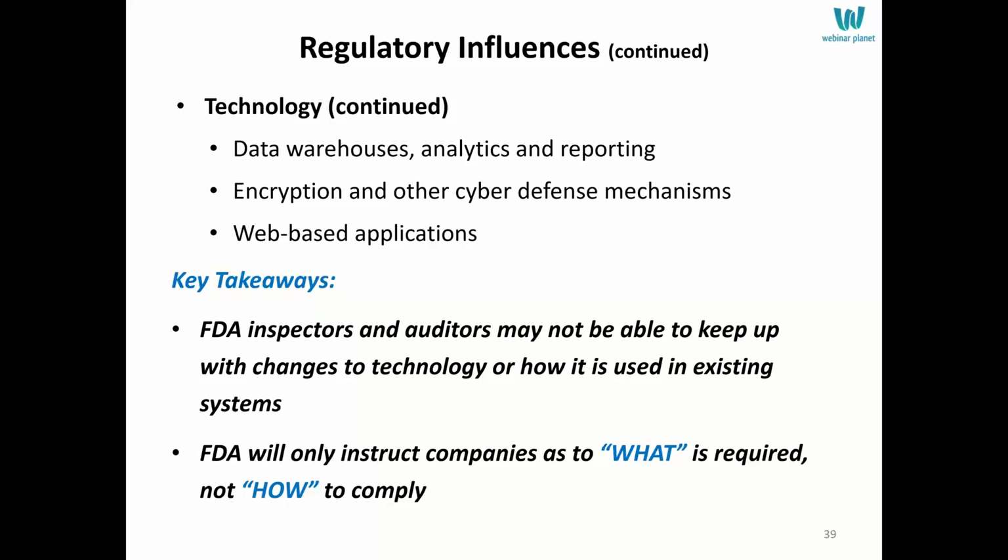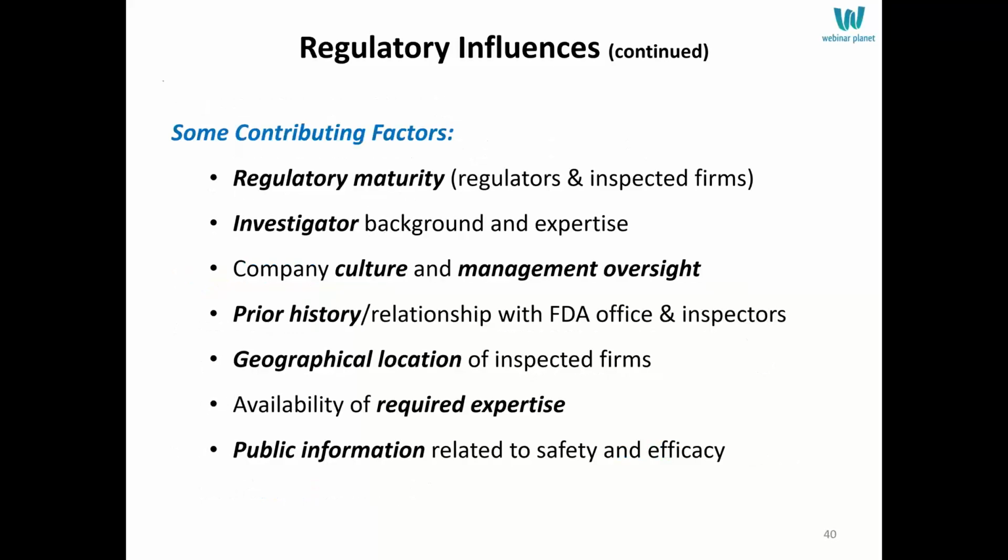So it took them 19 years to really get out there and start applying what they should have known in the first place, or be able to go to industry and make the right judgments when they're doing an audit. And again, FDA only instructs you as to what is required. They will never tell you how to comply with that requirement. They're never going to give you step-by-step instructions. It's up to each company to determine how to comply based on a particular technology they're using.